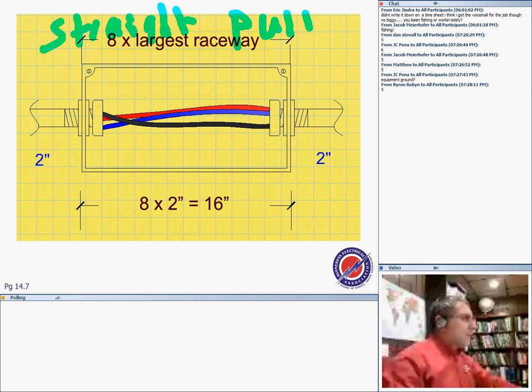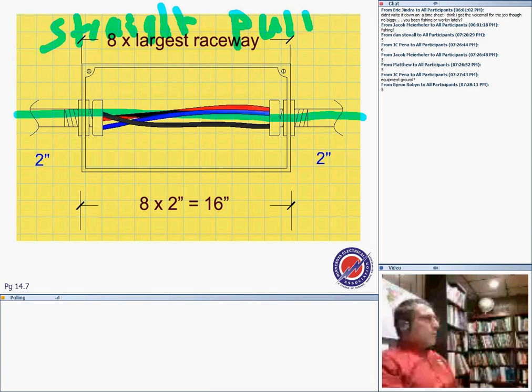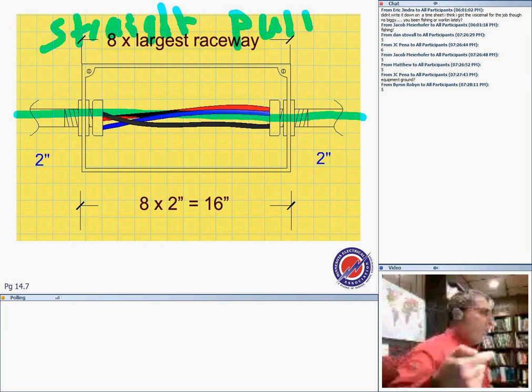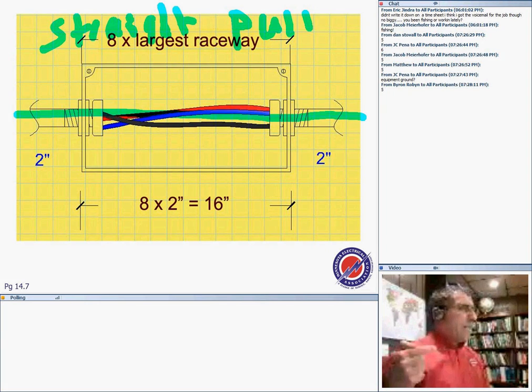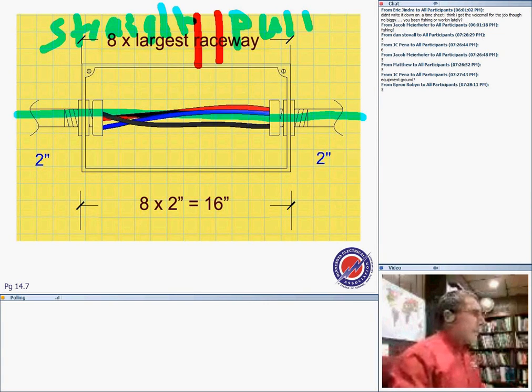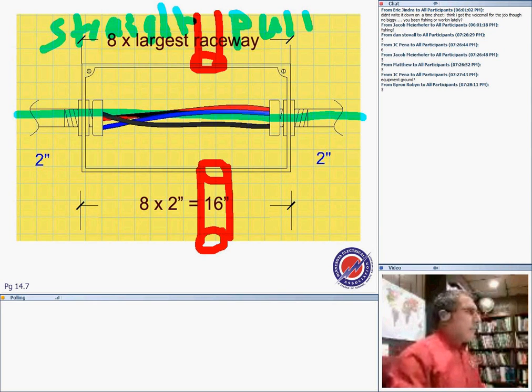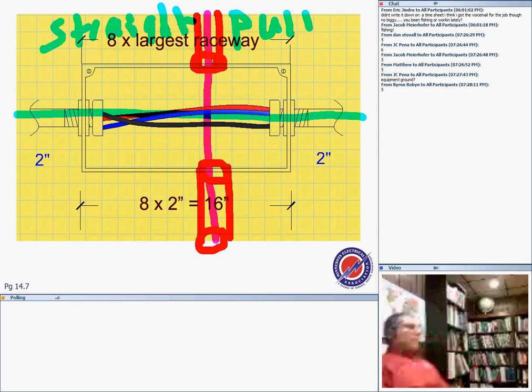Why, guys? Because I'm pulling the conductors from one wall to the opposite wall. That's a straight pull. You're entering from one wall and exiting immediately from the wall opposite to where you entered. Let's make a straight pull. If I bring a conduit from the top here and enter from the bottom here, this all will be a straight pull, right? The conductor is coming right through it. Well, that's a straight pull.